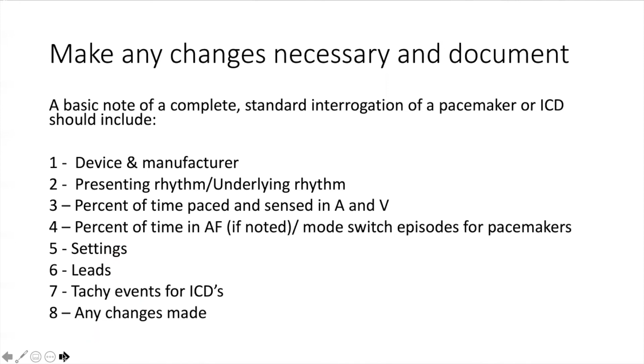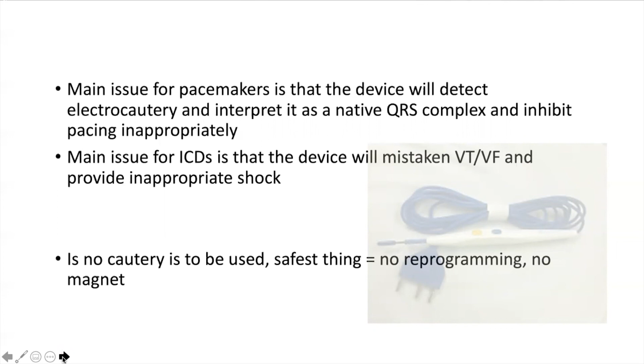All right, let's talk about what if you get called overnight to the OR to reprogram a device or to assess it. So the main issue for pacemakers is that the device in surgery will detect electrocautery and interpret it as a native QRS complex and inhibit pacing inappropriately. The main issue for ICDs is that the device will mistake it for VF and could provide an inappropriate shock. However, if no cautery is used, the safest thing is just do nothing, no programming, no magnet. There's not going to be any issue.